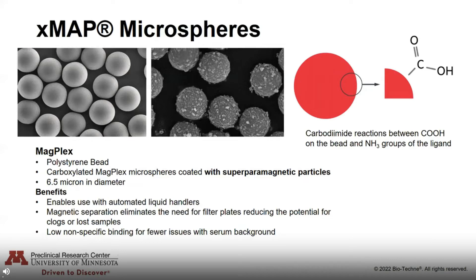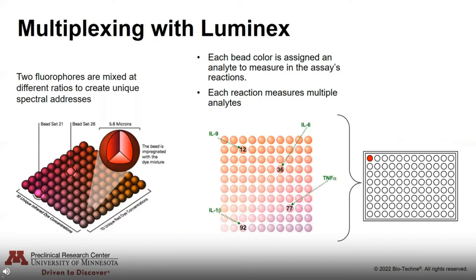xMAP works using microspheres — small beads coated with magnetic particles that have multiple binding sites, allowing detection of multiple analytes. The magnetic particles allow magnetic separation, which eliminates the need for filter plates or complicated washing steps — you simply use a magnet to draw the beads to the bottom and remove the wash buffer. With the Luminex multiplex assays, two fluorophores are mixed at different ratios to create unique spectral addresses. Each bead color is assigned an analyte to measure, and each reaction measures multiple analytes in one sample.